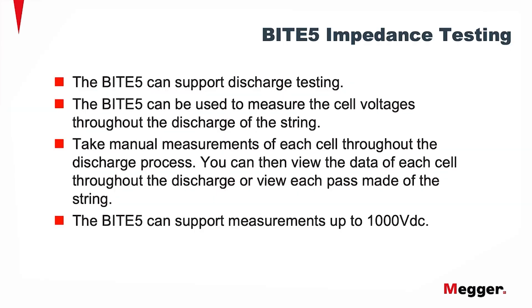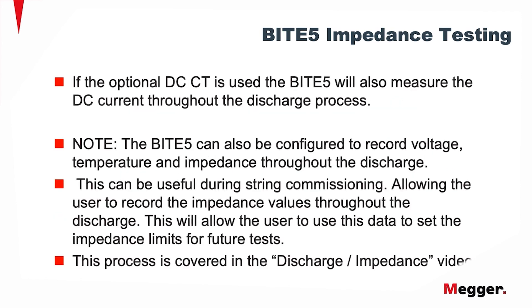The BITE5 can support discharge testing. It can be used to measure the cell voltages throughout the discharge of the string. Take manual measurements of each cell throughout the discharge process. You can then view the data of each cell throughout the discharge or view each pass made of the string. The BITE5 can support measurements up to 1000 volts DC. If the optional DC current clamp is used, the BITE5 will also measure the DC current throughout the discharge process.